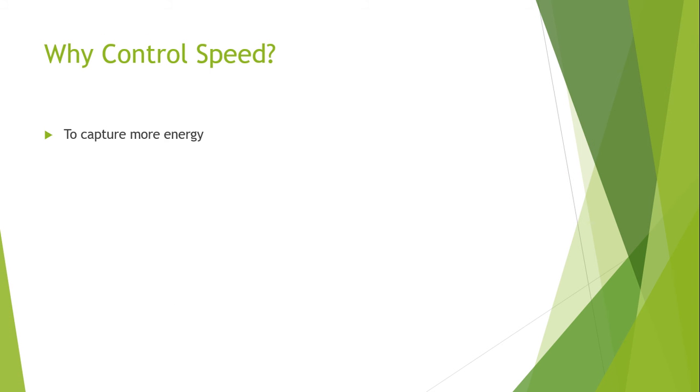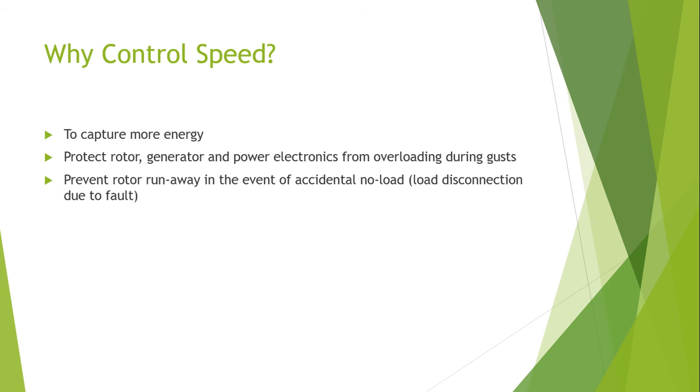Why should we consider controlling the speed? Speed is controlled to ensure that more energy is captured, and the rotor, generator, and power electronics connected with the wind turbine's power system are protected and ensured safe. The third reason is the prevention of rotor runaway in the event of accidental no-load when the load is disconnected due to fault conditions.